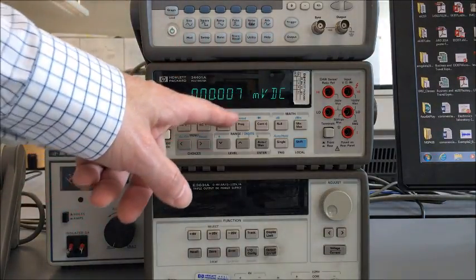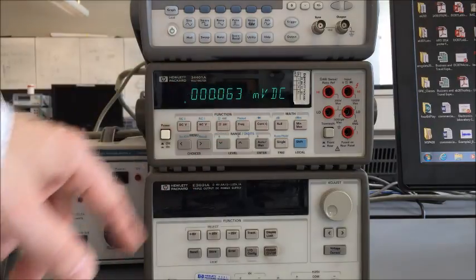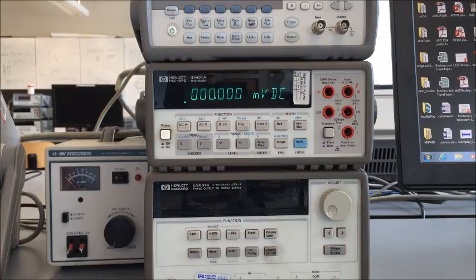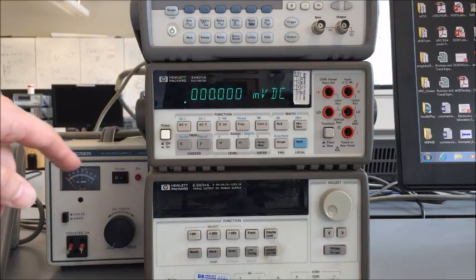We can see that on the screen right here. There's a little bit of voltage appearing across the terminals. That's most likely due to electromagnetic interference the machine is picking up. It's a very sensitive machine.